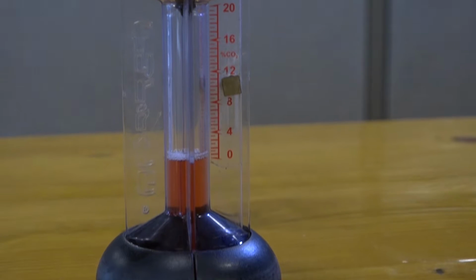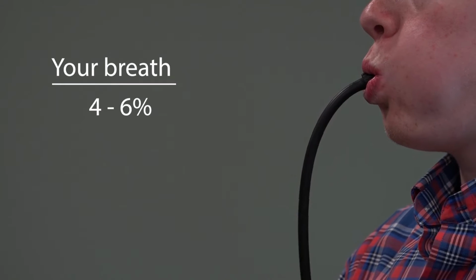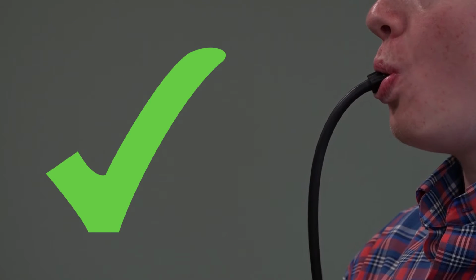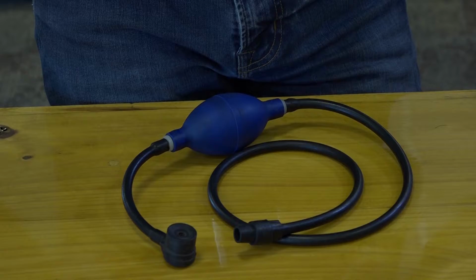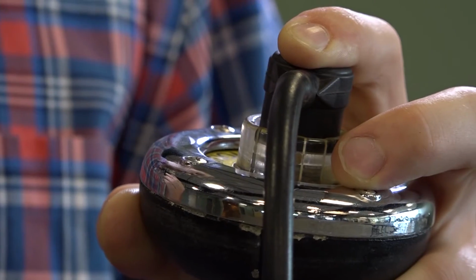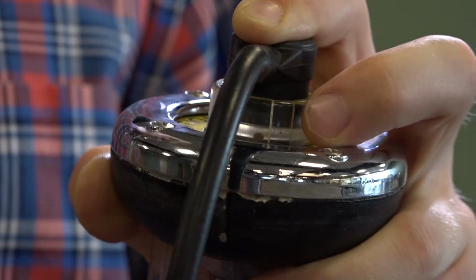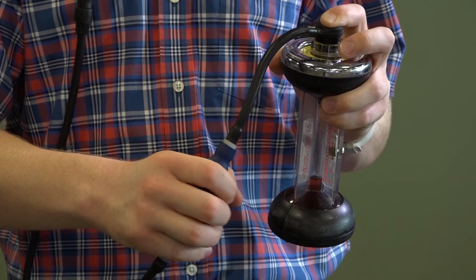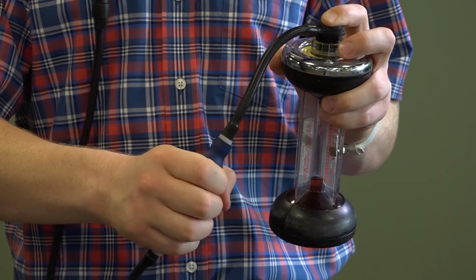Every day you use the carbon dioxide meter, start by testing the fluid strength with your breath. Because your breaths contain 4 to 6% carbon dioxide, that's the reading we're looking for. Disconnect the rubber hose from the probe and connect the hose to the meter by pushing the rubber connector down firmly. Take a deep breath, hold it for 4 seconds, and exhale steadily into the open end of the hose. While doing this, pump the aspirator bulb several times.